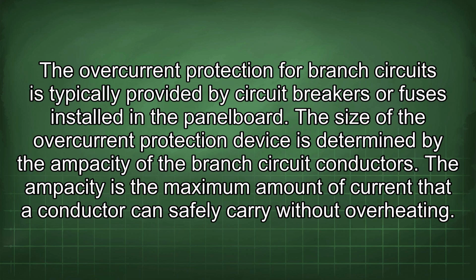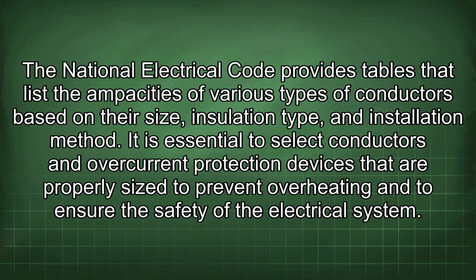The overcurrent protection for branch circuits is typically provided by circuit breakers or fuses installed in the panel board. The size of the overcurrent protection device is determined by the ampacity of the branch circuit conductors. The ampacity is the maximum amount of current that a conductor can safely carry without overheating. The National Electrical Code provides tables that list the ampacities of various types of conductors based on their size, insulation type, and installation method. It is essential to select conductors and overcurrent protection devices that are properly sized to prevent overheating and to ensure the safety of the electrical system.